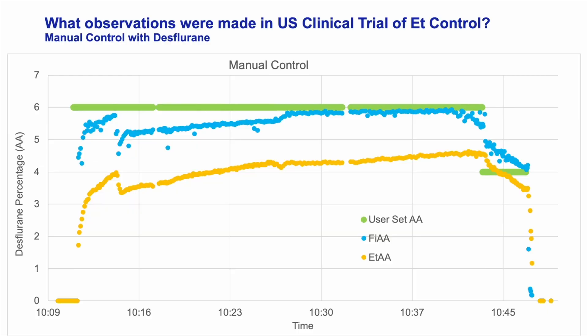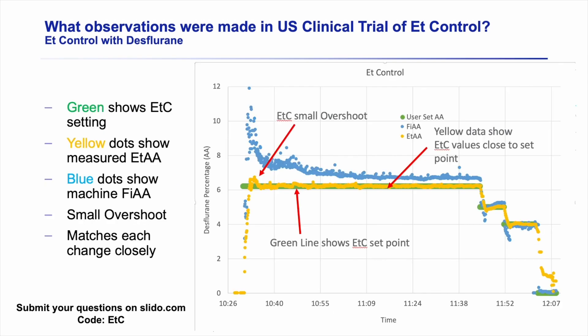Here are a couple of example cases. This first case did not use end-tidal control. The user was trying to get to an end-tidal value of 6% DES — that's the green line. The gold dots show the end-tidal value they actually got: 3.5%, 4%, for the exact reasons of agent cascade that Dr. Kennedy talked about. With end-tidal control, it's a very different story. There is a green line behind that gold line, but you can barely even see it because the measured value is right at your target value the entire time. When they make changes late in the case, very quickly the software reacts and gets you right back to that target value.